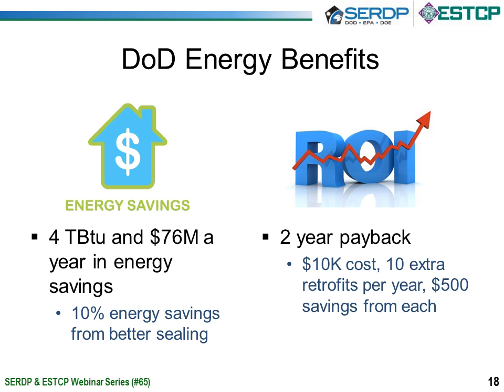If you think about somebody who's trying to retrofit an existing military base, one of the limitations to doing retrofits is the amount of time it takes to do the air leak testing, and the windows of opportunity in which you can do them. With a new technology like SonicLQ, you can do more testing and retrofit more of your buildings. It only takes an extra 10 tests a year and retrofits to those buildings, and the energy savings from sealing them up, to pay for the cost of buying the SonicLQ equipment, which we think will have a market cost of about $10,000.